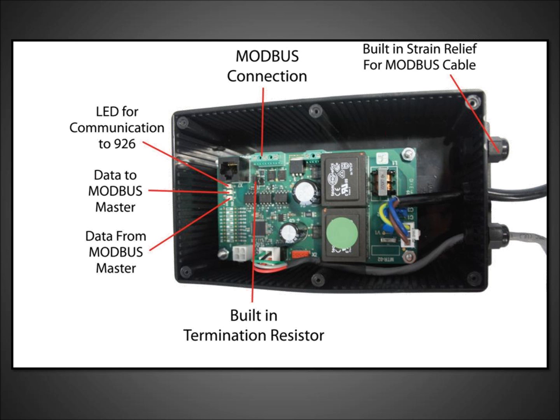Here we're looking into the box and looking at the board a little bit more. Starting from the left going down, there's three LEDs that we want to bring to your attention. There's an LED for communication, showing that you're getting communication from the 926. There's data to the ModBus master, and then there's data from the ModBus master. So these lights will flicker on and off. They are different colors, and they do represent active communication to a BMS system when you connect it up in a commercial installation.